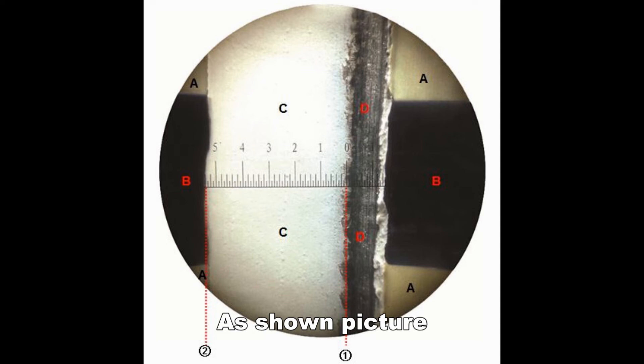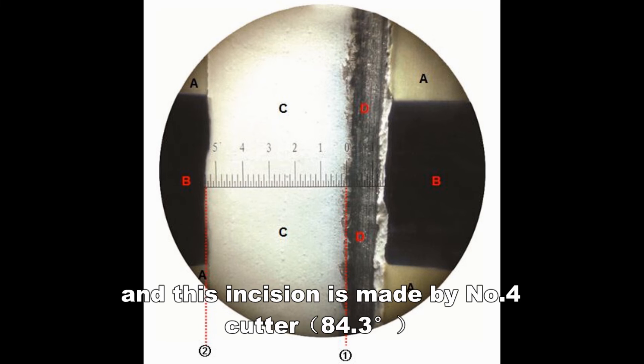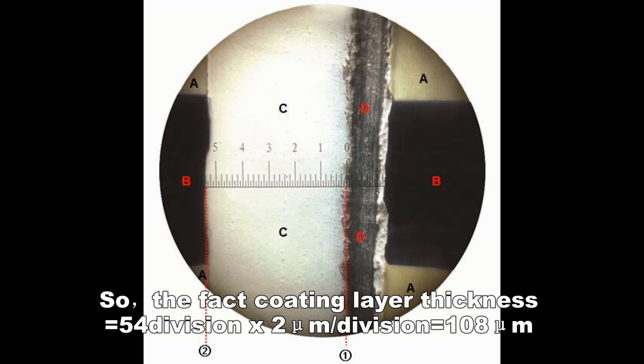As shown in the picture, the distance from line 1 to line 2 is 54 small divisions. This incision is made by number 4 cutter at 84.3 degrees. So the actual coating layer thickness equals 54 divisions × 2 μm/division = 108 μm.